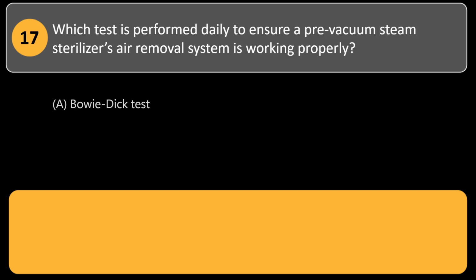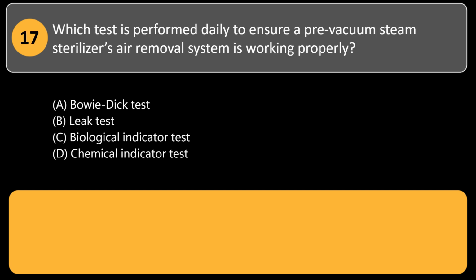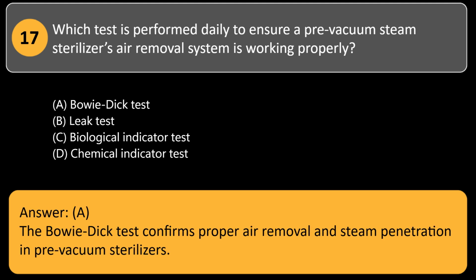Which test is performed daily to ensure a pre-vacuum steam sterilizer's air removal system is working properly? A. Bowie-Dick test. B. Leak test. C. Biological indicator test. D. Chemical indicator test. Answer: A. The Bowie-Dick test confirms proper air removal and steam penetration in pre-vacuum sterilizers.